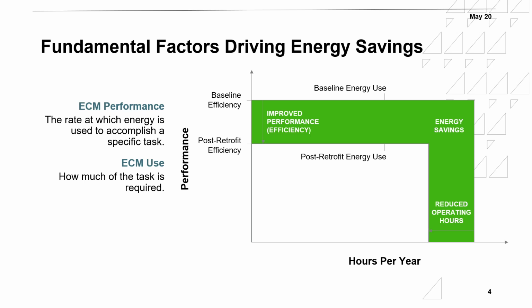As we can see here on the screen, the baseline efficiency was at the top, and then the post-retrofit efficiency is reduced a little bit. Also, the hours per year have reduced from the baseline to the post-retrofit, and all that green area here is basically savings. That's due to a reduction of energy consumption because we have more efficient equipment or a better control strategy, and reduced operating hours because we're reducing the number of hours that ECM or that particular system is being used. ECM performance is the rate at which energy is used to accomplish a specific task, and ECM use is how much of the task is required. So to reduce energy consumption, preferably we need to look at both and try to reduce both.